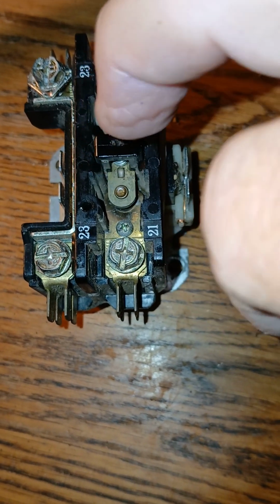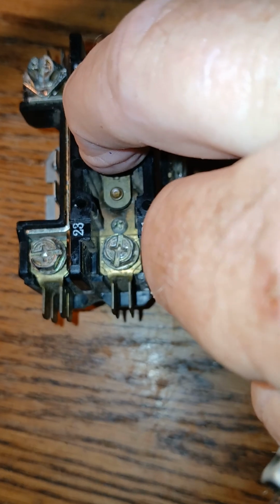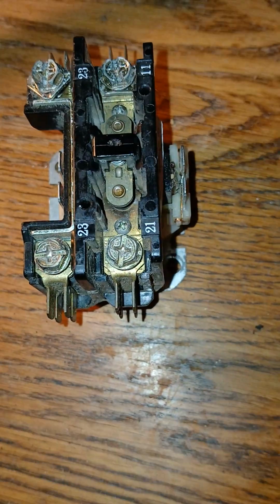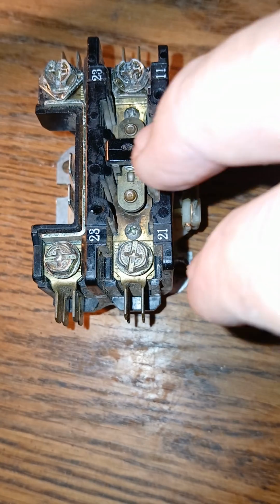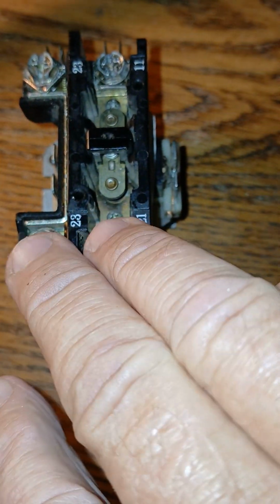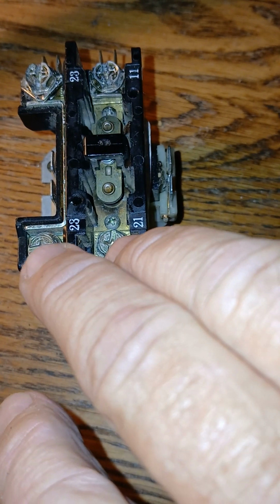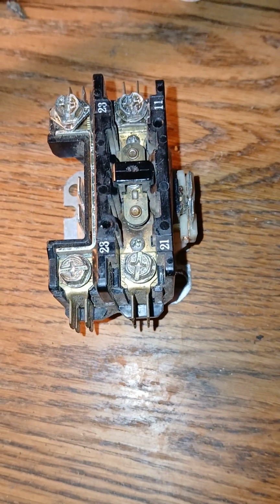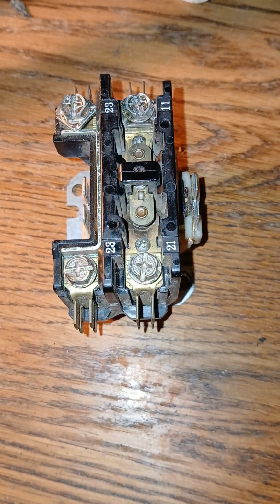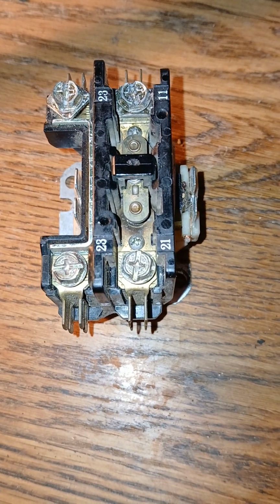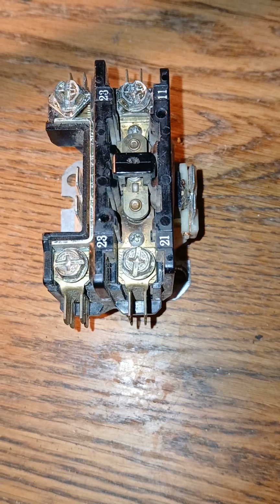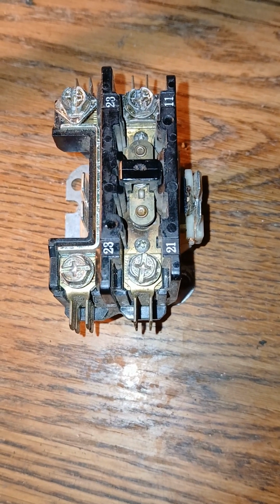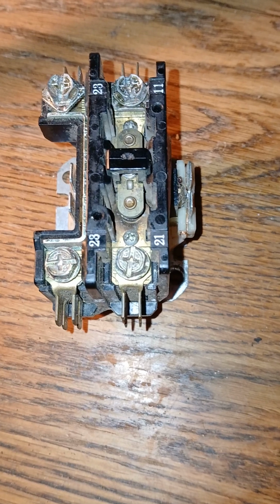And as one can see, the little contacts make contact, and then your voltage would jump over. So again, if the thermostat was met again and de-energized, it would pop up. You would have voltage here, no voltage here. Now, if it becomes energized, this pushes in. If it's working correctly, it energizes from the low voltage, the two terminals on the side. Then you would have 120 here, 120 here. It's just kind of a way to think of it to start and stop high voltage, to bring high voltage to a particular area. But there are times when one needs to cut it off so that something doesn't just keep running all the time and burn something up.